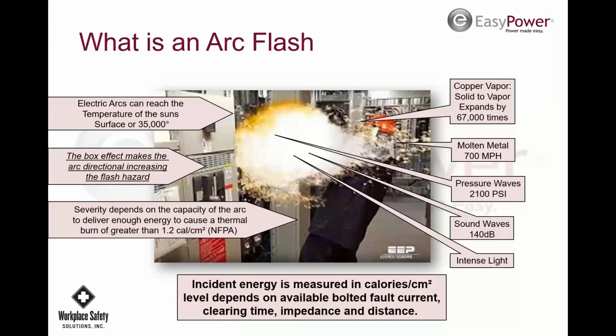And everyone has their own specific time current curve. So when you're talking about this incident energy level, the incident energy is directly proportional to clearing time. Directly proportional to clearing time. That's pretty important because if I'm working downstream from a fuse, I know that a fuse can operate really quickly. It will open up in as little as a quarter of a cycle. Remember, we have 60 cycles per second. So a quarter of one cycle is a very small amount of time.